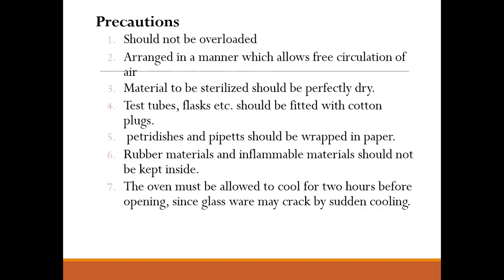Precautions: number one, the oven should not be overloaded. Number two, it should be arranged in a manner which allows free circulation of air. Material to be sterilized should be perfectly dry.